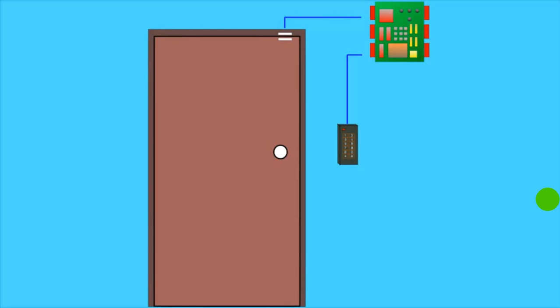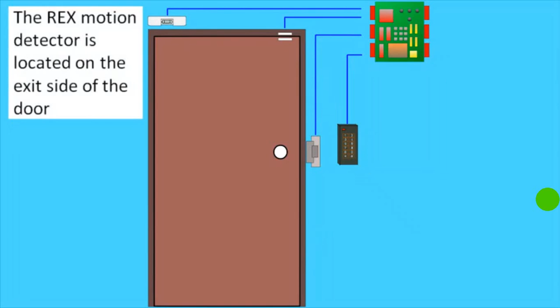A typical Cantech setup for access control is an access controller. This is what takes the decision to let people in or out. It also manages unlock schedules and many other things. A reader or keypad. This allows you to enter your unique credentials to gain access. A door contact. This allows the controller to see if the door is open or closed. A door strike or magnetic lock. This will release the door when you get an access granted. A request to exit. This allows you to exit an area without entering any credentials.